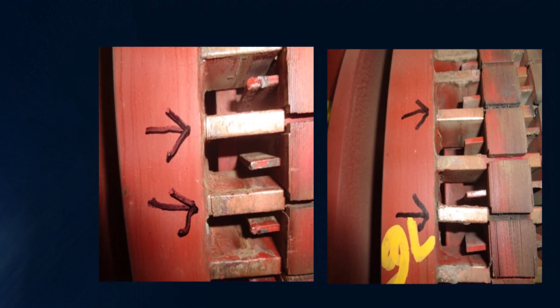It's bad. If you have markers on your rotor, it's bad—the yellow writing is never a good thing. One thing to point out: you mentioned earlier, open bar versus closed bar design. These are open bar designs with a higher risk of secondary damage to the stator, but we caught it early enough, flagged it, tracked it, trended it, and made a decision at the right time. You can see the cracks are obvious, but the slots where the rotor goes through the iron are not burning up.